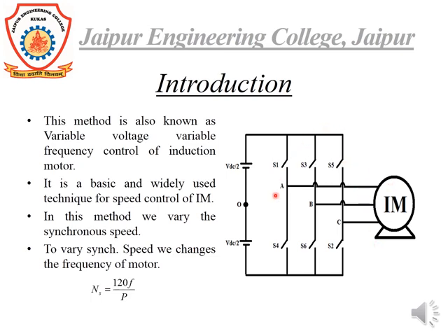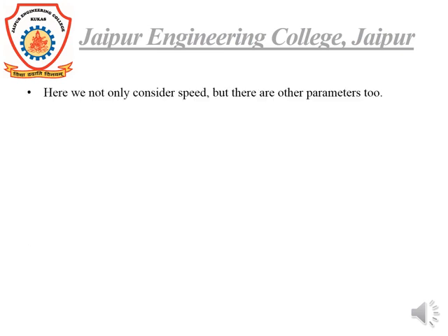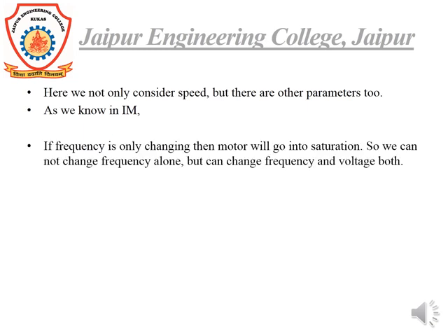This is the basic diagram where the induction motor is fed from a three phase supply. Here we not only consider the speed, but there are many other parameters which we have to change to control the speed. Once we change the frequency in the induction motor, many parameters will change. If only the frequency is changing, then the motor will go into saturation. So we cannot change frequency only, but we can change frequency and voltage both.